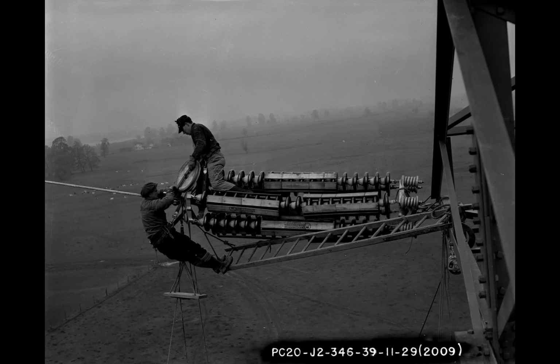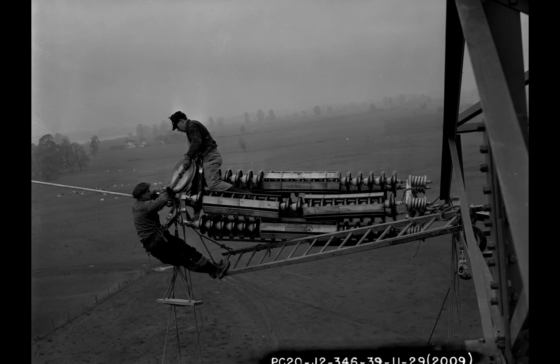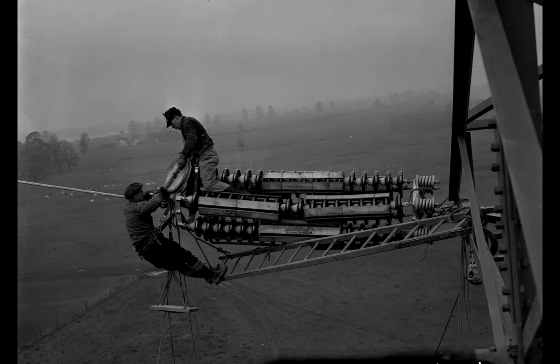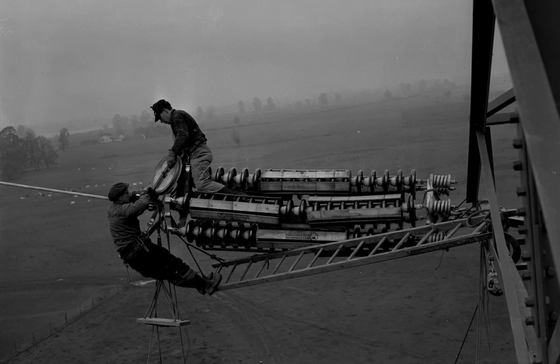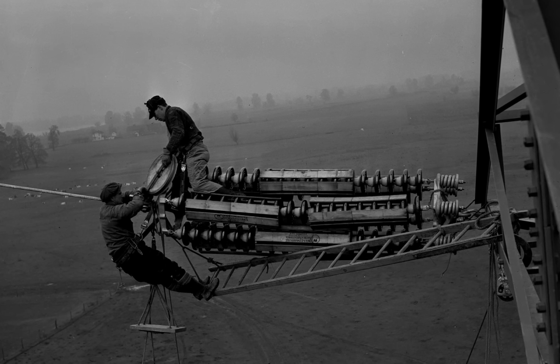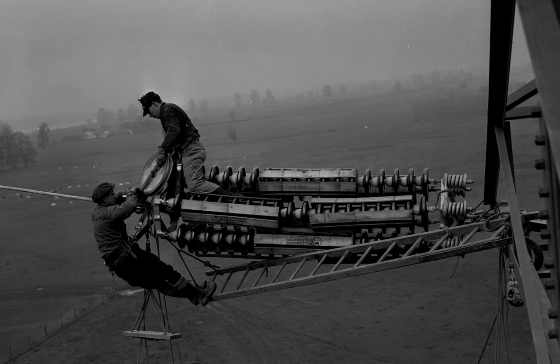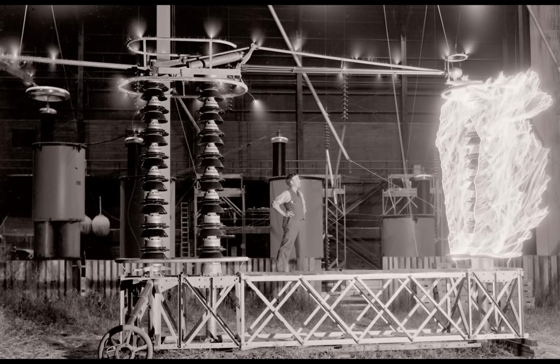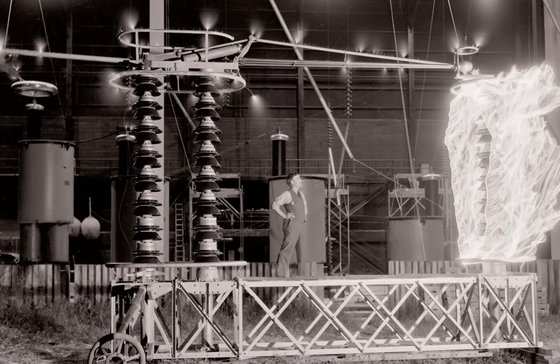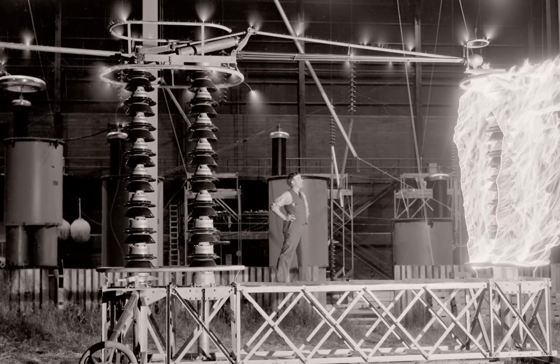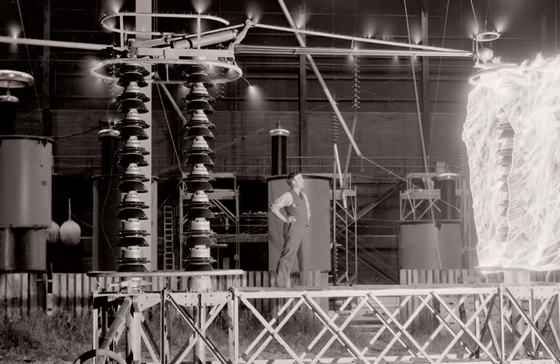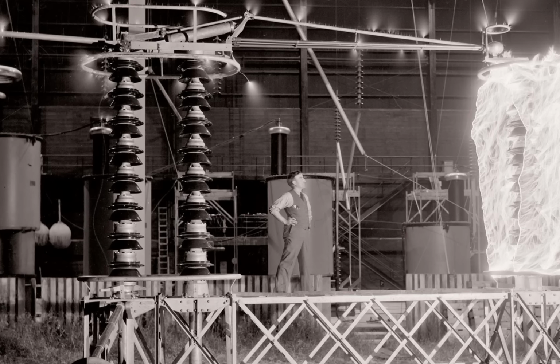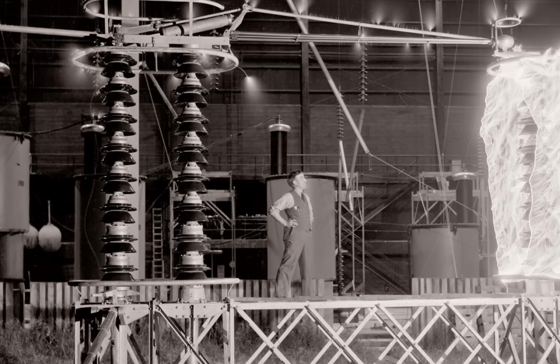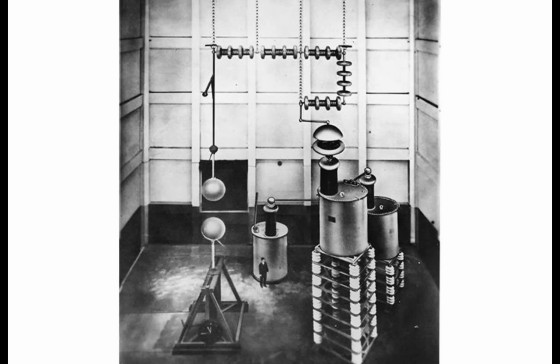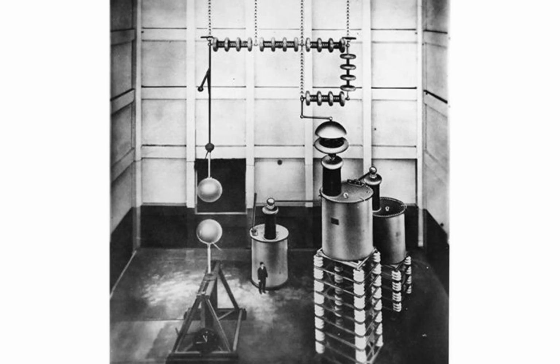At 110,000 volts, pin-type insulators weren't an option at all. No reasonable pin-mounted design could survive that electrical stress without becoming so large and so heavy that no wooden crossarm, and arguably no tower, could support it economically. Utility engineers were blunt about the math. Continuing to scale up the old design would mean insulators weighing tens of pounds each, multiplied across thousands of poles, adding catastrophic cost and weight to a transmission system already pushing the limits of what was buildable.